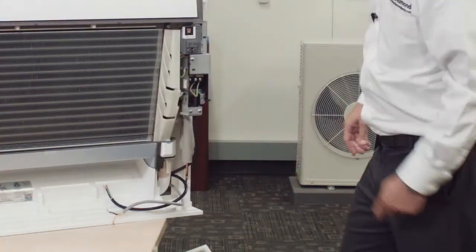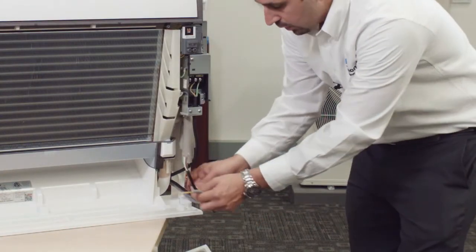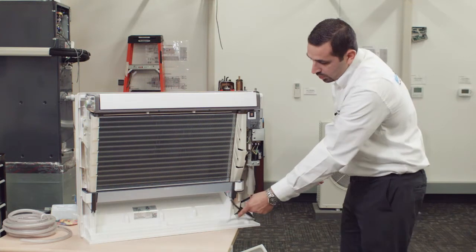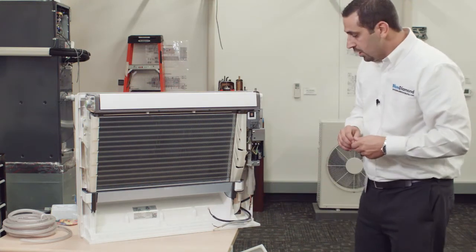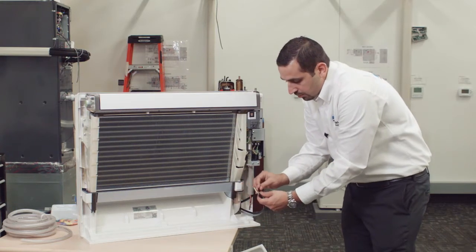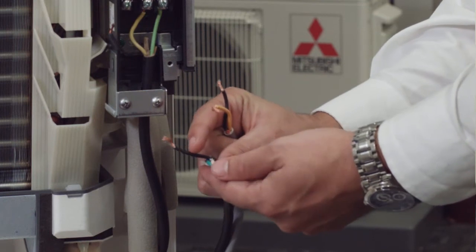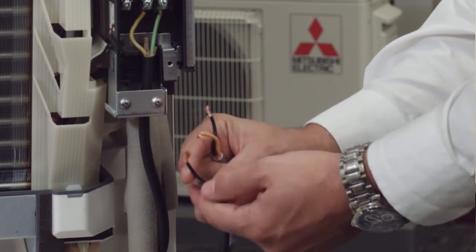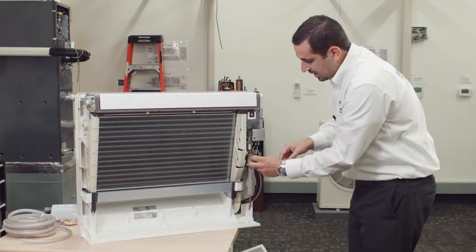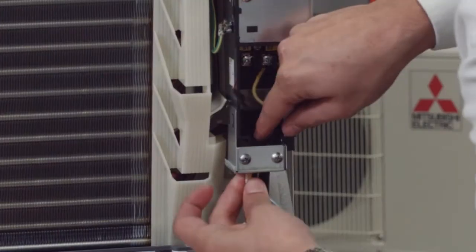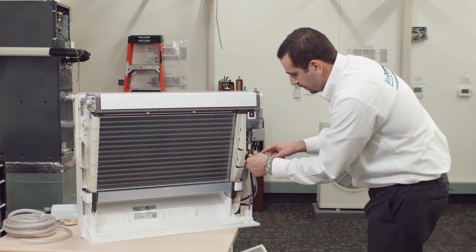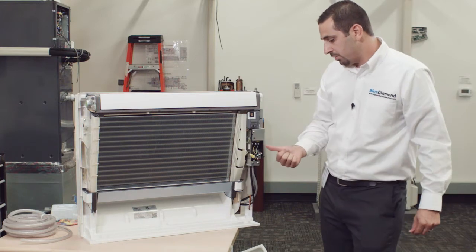Now that you've got your electrical wires pulled through to the front of the unit, what we'll work on now is actually installing the electrical off of the control panel. We're going to run S1 through my pump. In this particular case, the S1 wire is black, so we're actually going to wire nut that to both black wires on the pump. This black wire is what we call our L1, that's going to power one of the legs of power for the pump. This other black wire from the pump is from the alarm side, that's your common. So when you have those three black wires put together, you've brought your voltage in to the common of the pump and then the L1, which is one power leg of the pump.